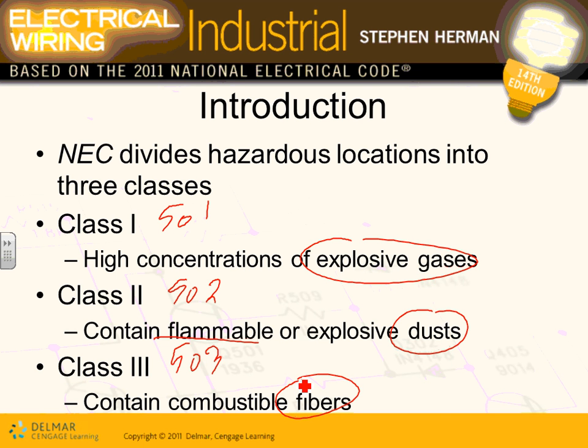Any comments, guys, about the classification? Class 1, Class 2, and Class 3. Can you give a thumbs up, Chad? We know the difference between them. One is flammable gas, and the other ones are ignitable dust and combustible fibers. Based on these locations, we classify them into three different locations. Why do we care? Because when you go bid on a place that has a refinery, that's going to cost you probably twice as much to install the same lighting fixture, receptacles, and air handling unit as if it wasn't an explosion or hazardous location. Do you guys see why it's important? Everybody understand why it's important? It's expensive equipment, expensive wiring methods that you have to use in these areas in order to prevent what? Fire and explosion. Your goal is to prevent fire and explosion.